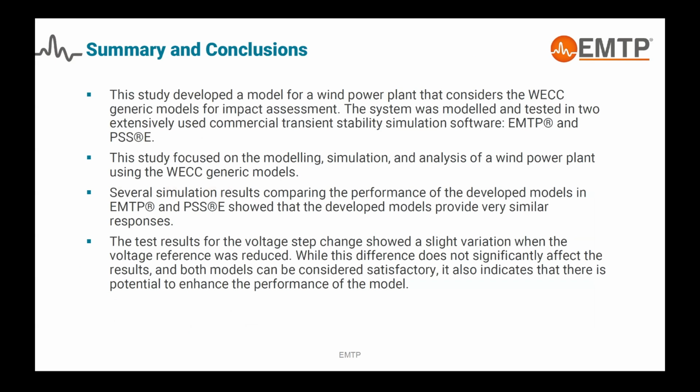Yeah, in terms of conclusions, just to highlight that in this case, both models responded very well. And even if you have one model with more generators and more feeders, and one using a single machine model, and even running some tests in a different way, from the dynamic perspective you can get the same results, right?